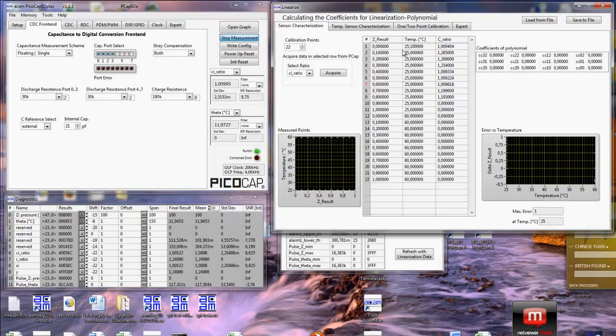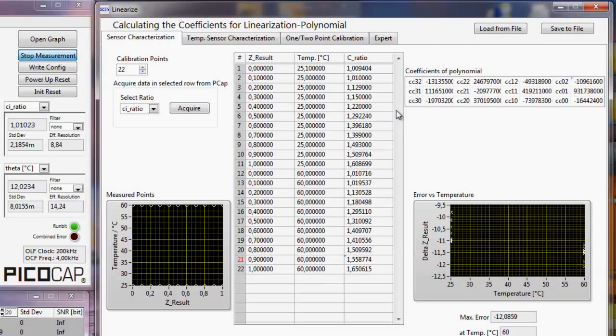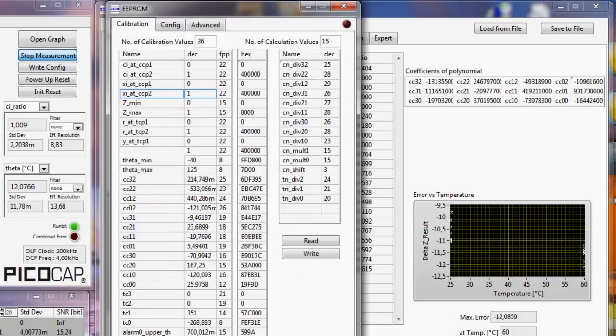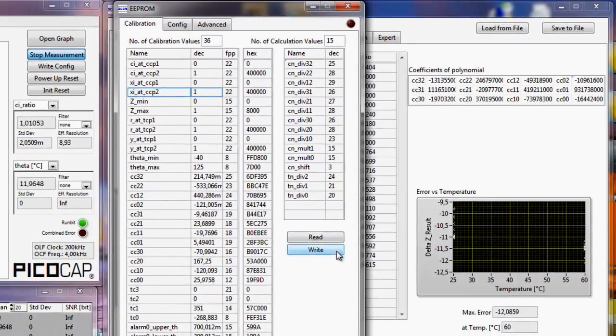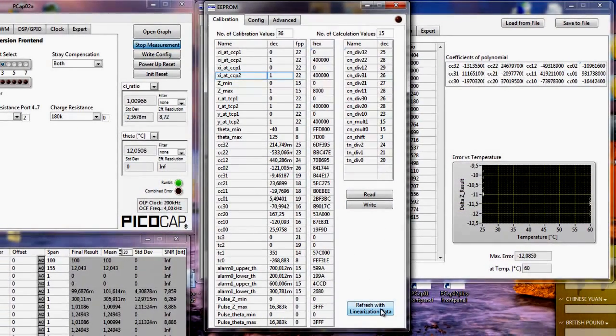Once you have done that with real values at 2 or even more temperatures, then the coefficients of a third order polynomial will be calculated here automatically. So I just filled in the C ratio column with some assumed values, and you see the coefficients are calculated correctly. Once you have the coefficients, you can go back to the EEPROM page and say refresh with linearization data to import the coefficients calculated here to the corresponding parameters in this window.